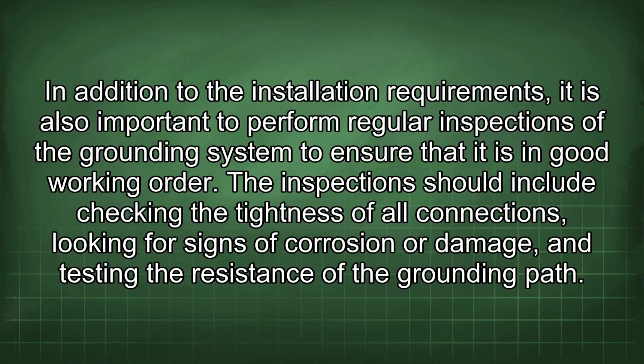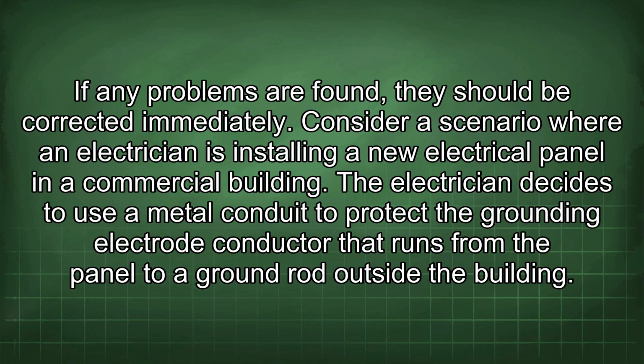In addition to the installation requirements, it is also important to perform regular inspections of the grounding system to ensure that it is in good working order. The inspection should include checking the tightness of all connections, looking for signs of corrosion or damage, and testing the resistance of the grounding path. If any problems are found, they should be corrected immediately.